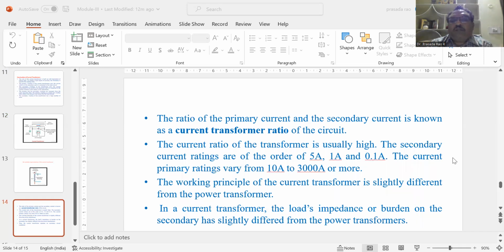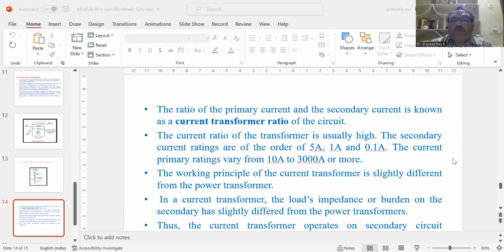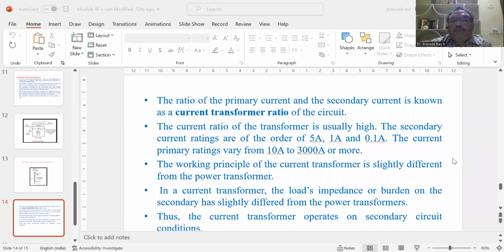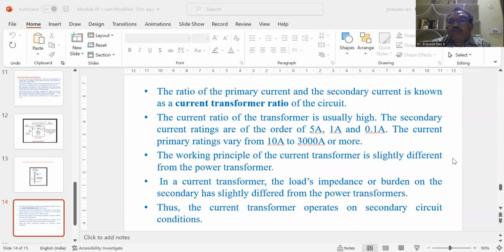The secondary current ratings are of the order of 5 amperes, 1 ampere, and 0.1 amperes. The primary current ratings vary from 10 amperes to 3000 amperes and more. The working principle of a current transformer is slightly different from the power transformer. In a current transformer, the load impedance or burden on the secondary is slightly different from that of power transformers. Thus, the current transformer operates on secondary circuit conditions.